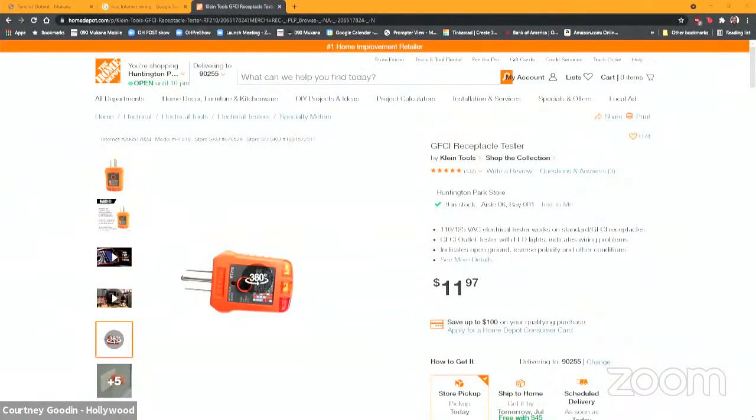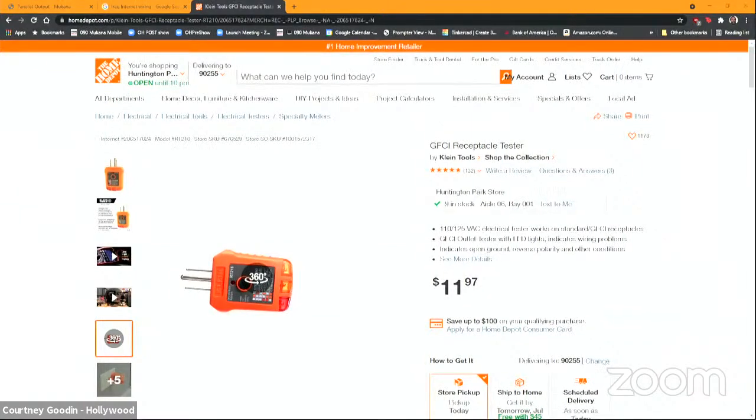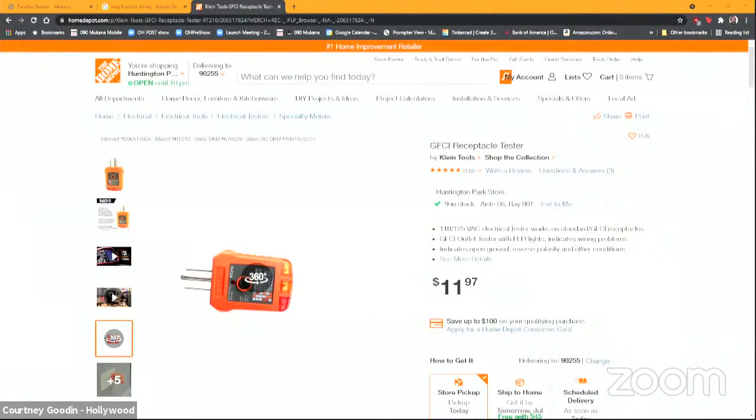One thing I recommend always having is something like this, which you can buy very cheaply and carry in your bag, because the one thing that's going to blow up equipment when you get to somebody else's location is improper wiring. It will tell you if the hot and neutral are reversed and if you've got a good ground. It also has a button for testing. It's called a GFCI receptacle tester, and the button temporarily shorts the neutral or the hot to ground to test if the GFI plug you're plugging into works.